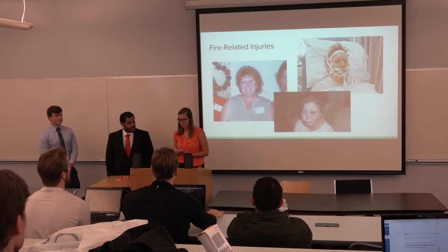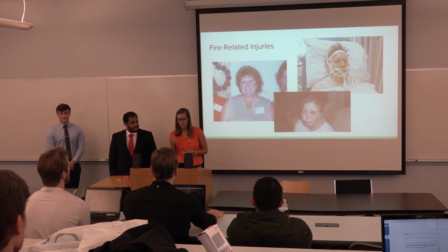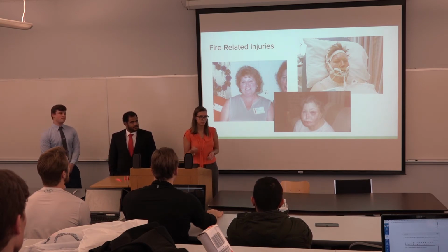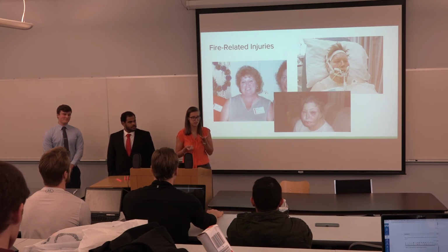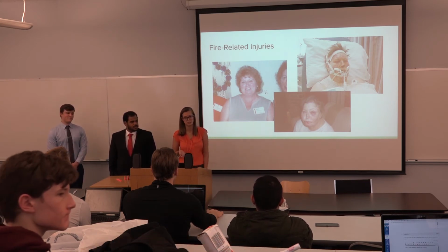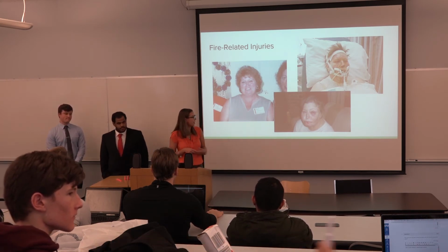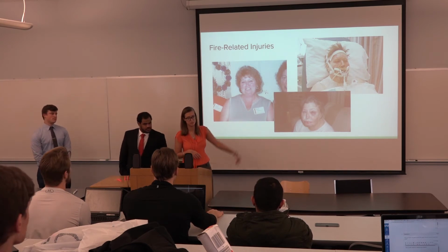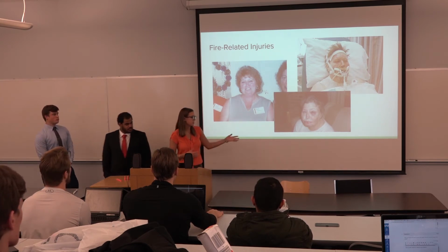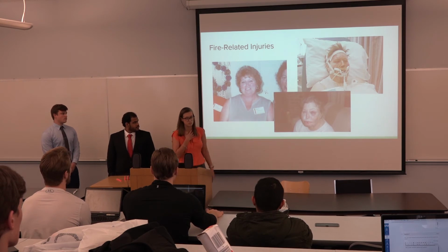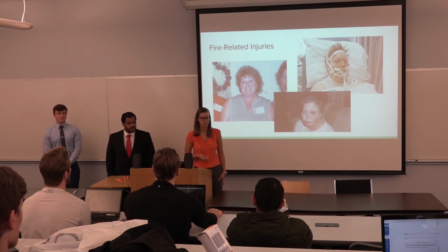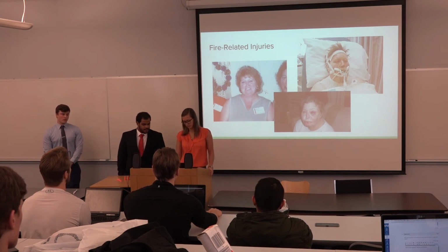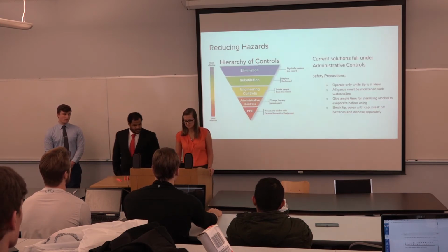This woman went in for a simple thyroid procedure, and someone was using this portable cautery device. They set it down onto the patient, and it ignited. It used oxygen from her oxygen mask, and as you can see, it caused very severe burns. This bottom picture is her 3 years after the original incident. Her neck and chest were also burned, but her face is severely disfigured even long after. So we really wanted to focus on preventing these kinds of fires.